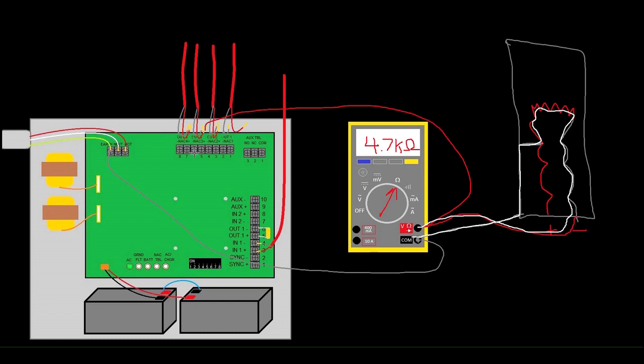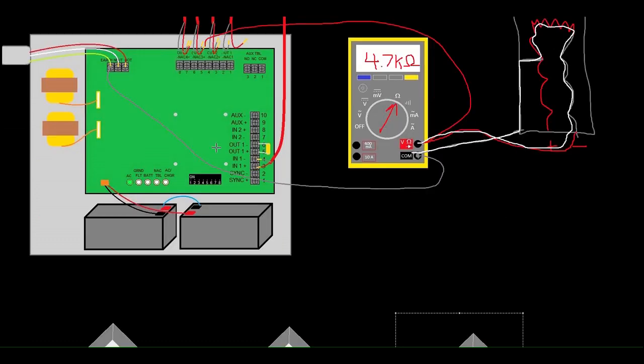Another option would be to put a different valued resistor. So if you know you have a 4.7 at the end of the circuit, maybe you put a 47 or a 10k or something to tell you what your panel is. It's arbitrary, obviously, so you would just make that up. You would know, okay, I put a 10k at the panel, so now anytime I go to the field, meter of 10k, that represents my panel.